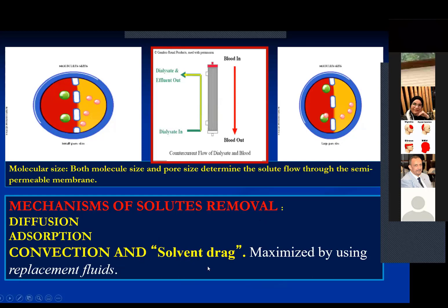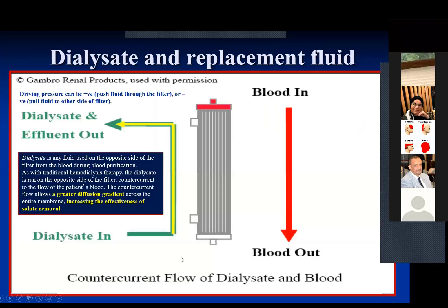Solvent drag requires the solvent, dialysate, or replacement flow to pass through the filter, which withdraws unwanted molecules and pro-inflammatory cytokines with it. There are different types of filters, differing in pore size and membrane material — either synthetic or cellulose. The most efficient is the synthetic one. Blood runs in one direction and dialysate or replacement fluid in the other direction to increase the efficacy of convection.